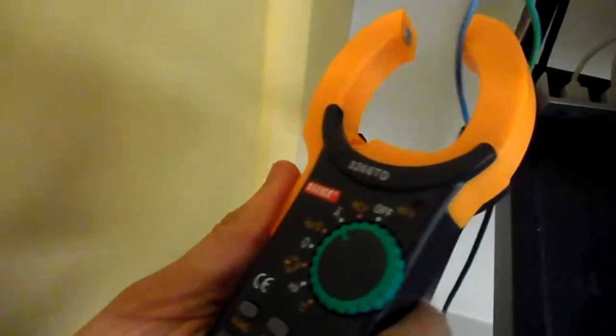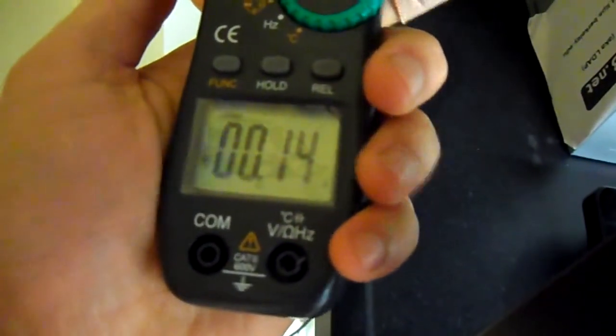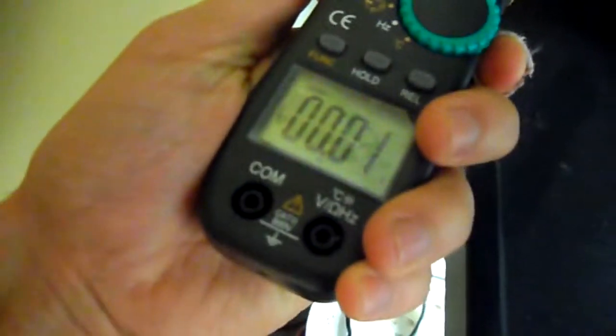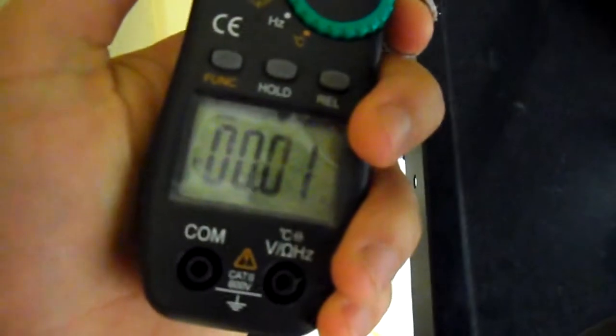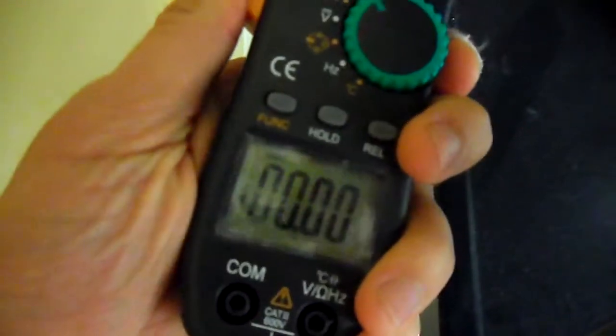If you clamp around the supply or around the return, you get the same value, which makes sense. If you clamp around the ground, as long as your equipment is operating correctly, there should be no current flowing here, unless there's a fault of some sort. So that's a good thing.